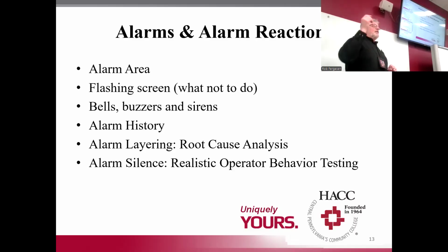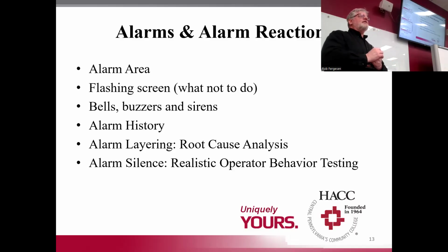All right, this is the problem, and this is the possible root cause. It shouldn't be very difficult to figure out for most systems. We're not dealing with Three Mile Island at most plants here. So always come up with a simple chart of root causes for possible alarms in your facility and put that on your HMI. We don't want bells, buzzers, and sirens in general.